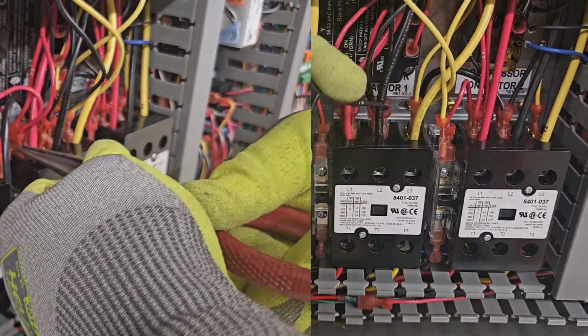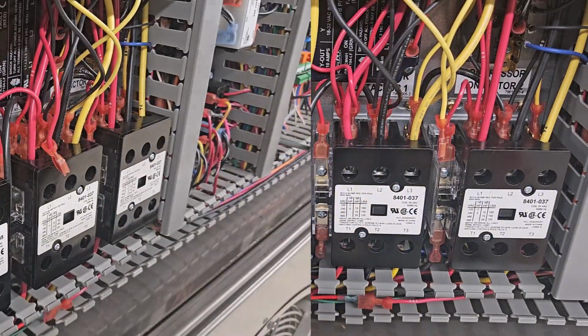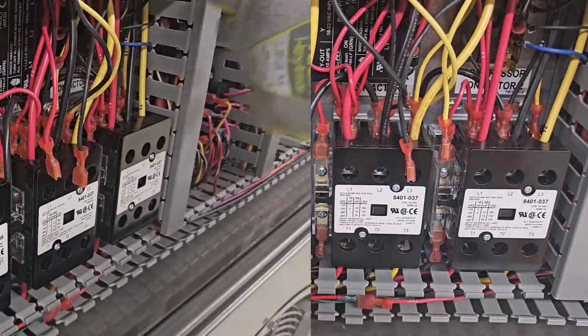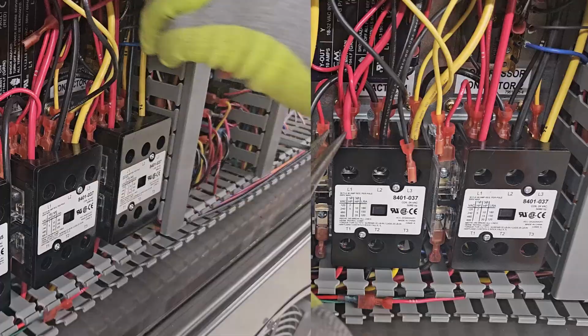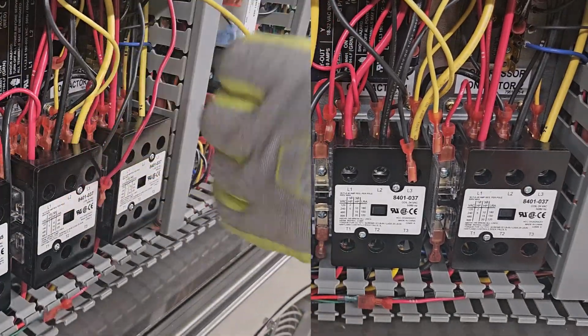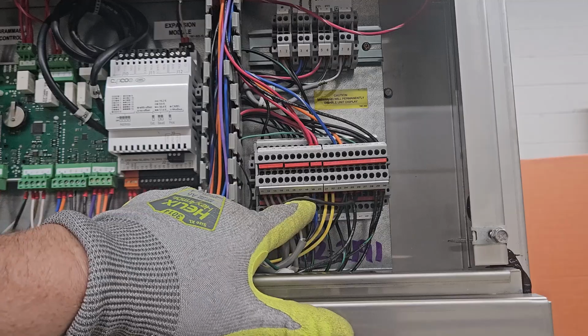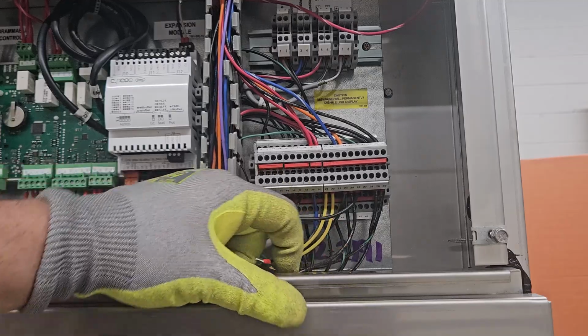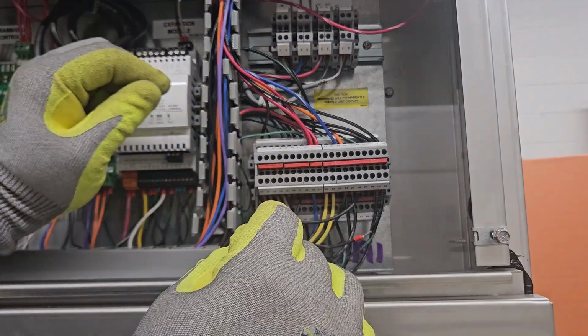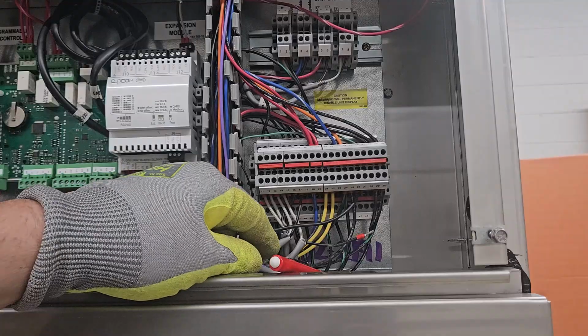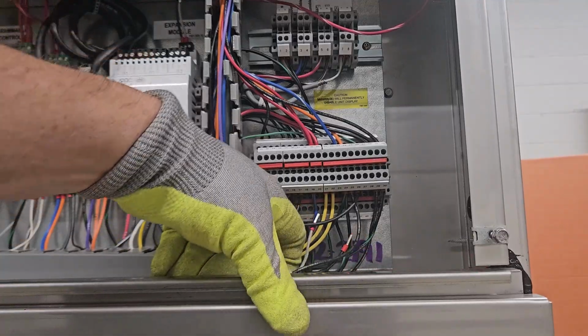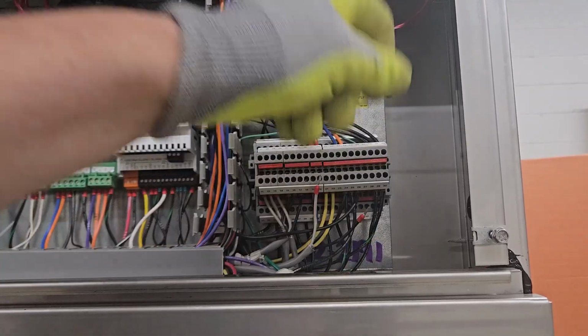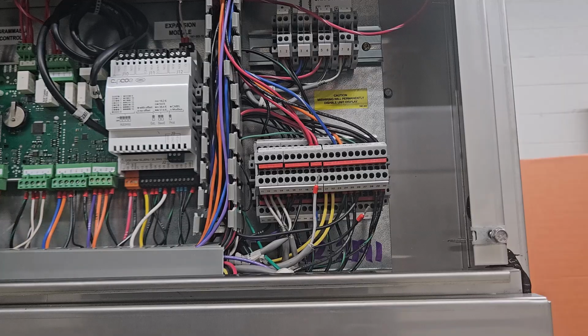If you are unsure which wires to remove, look at the schematic drawing and the wires will be numbered. You could also trace the wires from the indoor fan motor and find them that way. It may be necessary to remove the wires with a needlepoint pliers. The communication wires can be found on the right side of the unit and are attached to the terminal block. The wires should be labeled as indoor blower motor, or trace the wires back from the indoor blower motor to the correct terminals.